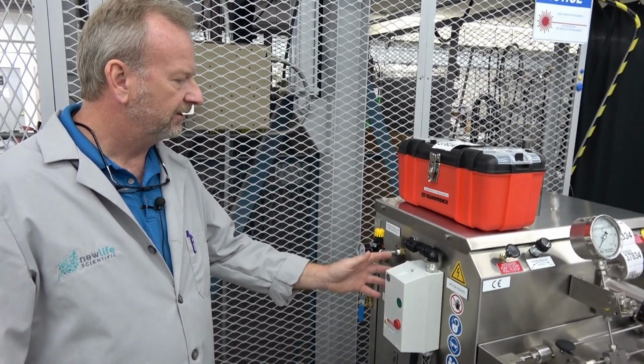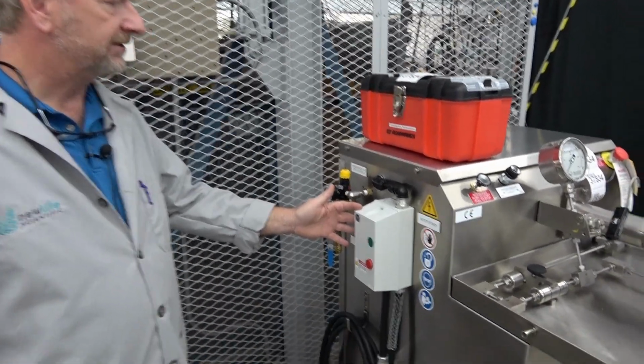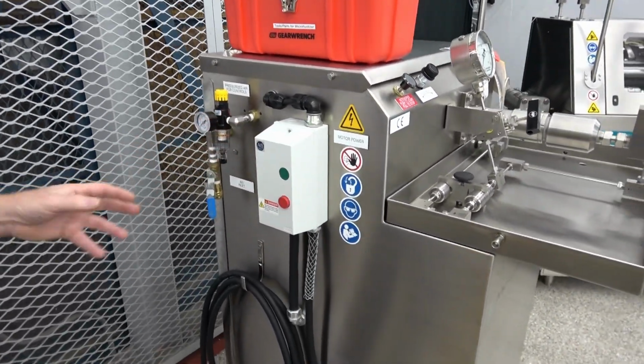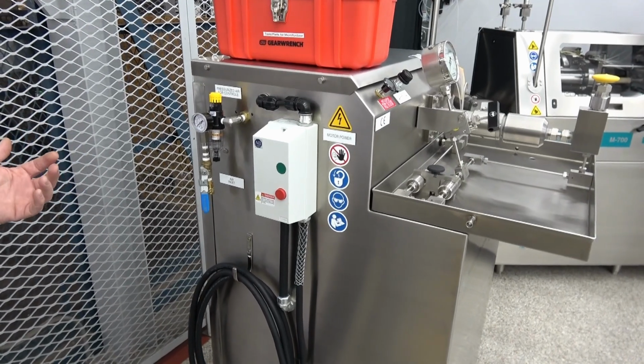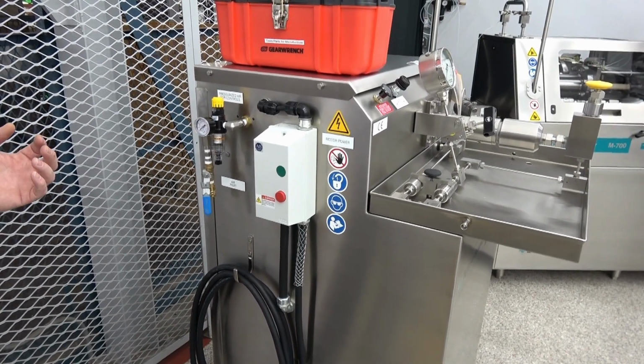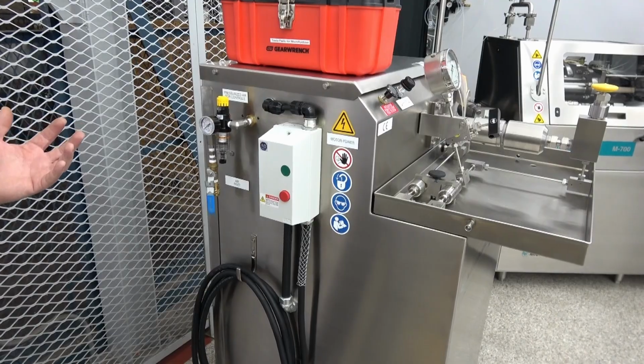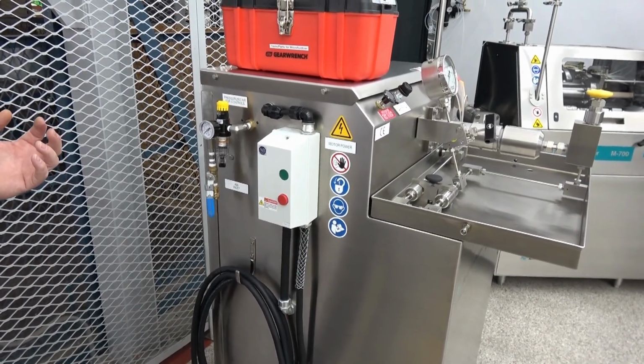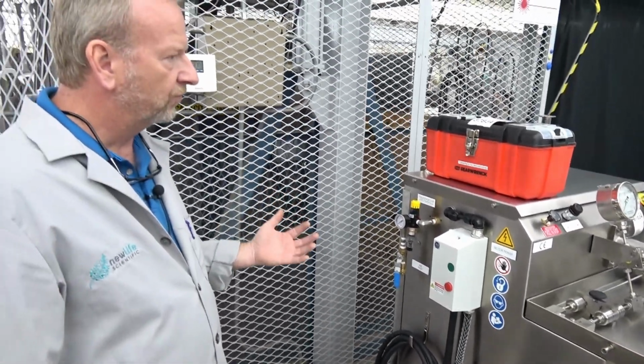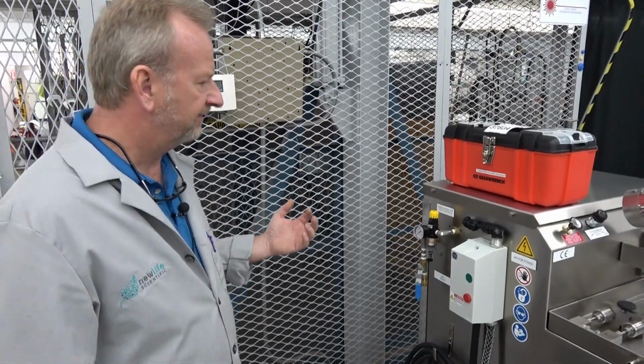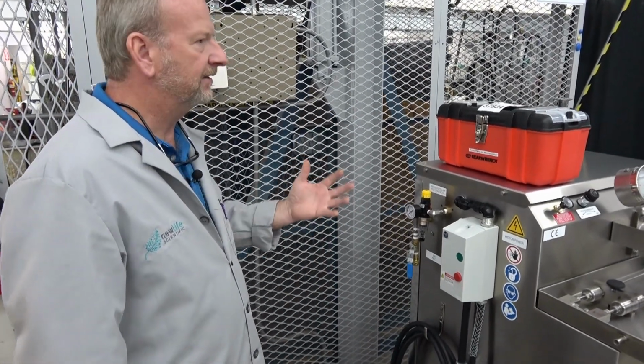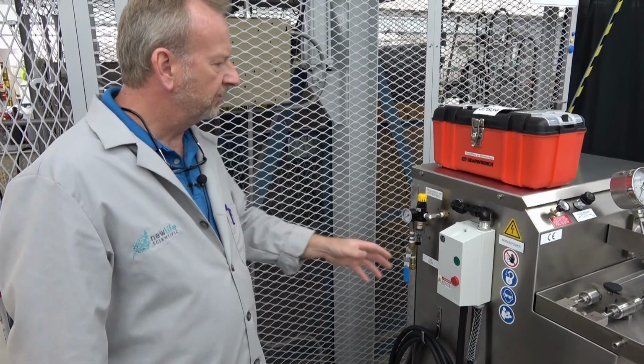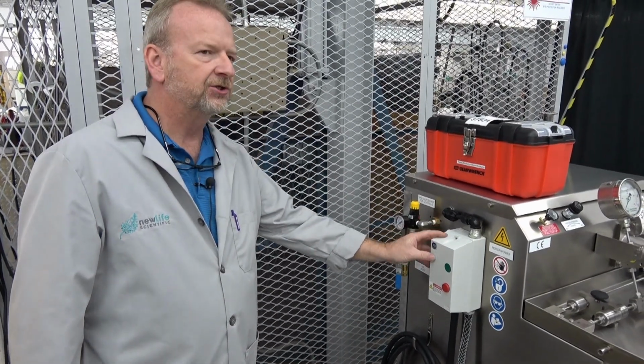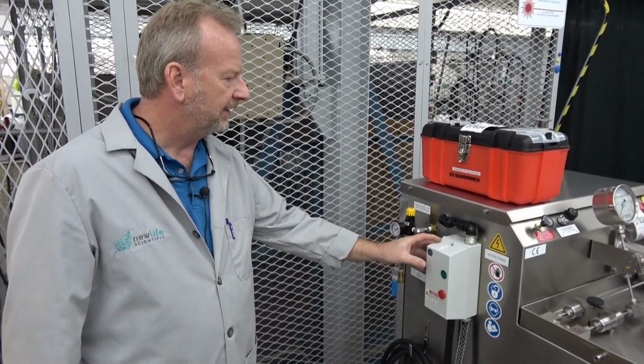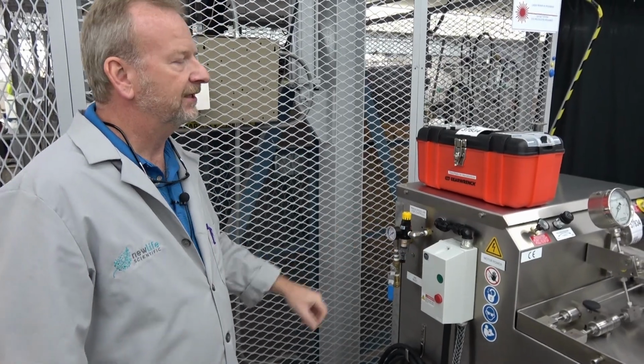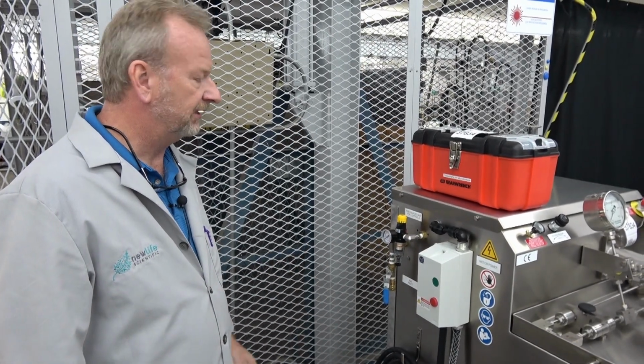It's probably right here in the starter box, which is being controlled off of the power source coming into it. Right now this one's 3-phase low voltage, and say we have a customer that needs it rewired for 400, since most 3-phase in Europe is 380 to 440 volts. In this starter, we'd simply need to change out the coil pack, a small component, maybe $25 depending on where you purchase it.